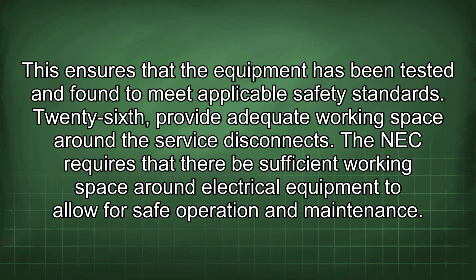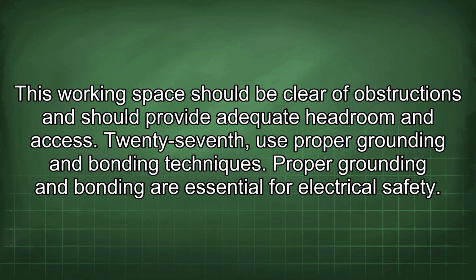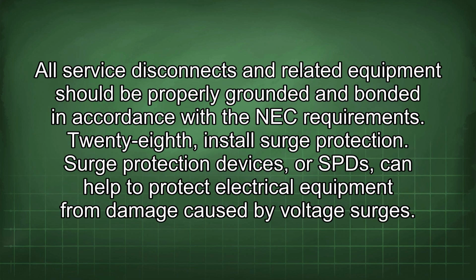26. Provide adequate working space around the service disconnects. The NEC requires that there be sufficient working space around electrical equipment to allow for safe operation and maintenance. This working space should be clear of obstructions and should provide adequate headroom and access. 27. Use proper grounding and bonding techniques. Proper grounding and bonding are essential for electrical safety. All service disconnects and related equipment should be properly grounded and bonded in accordance with the NEC requirements.